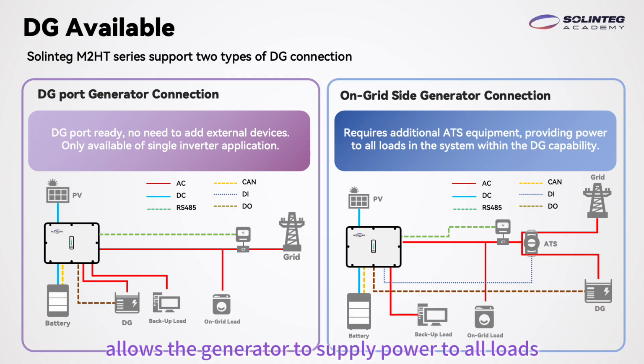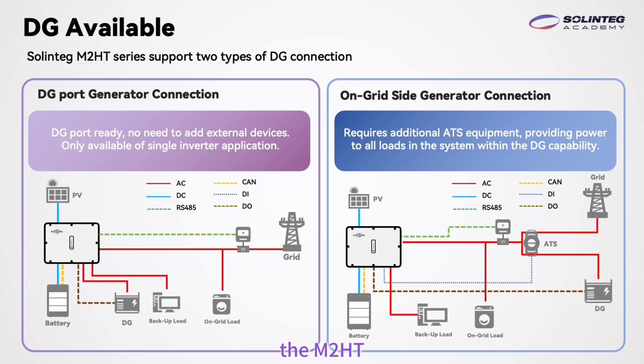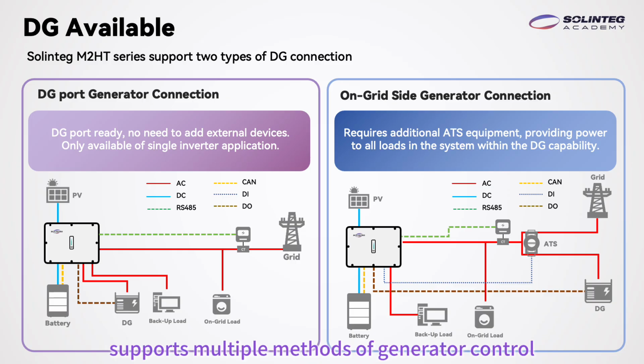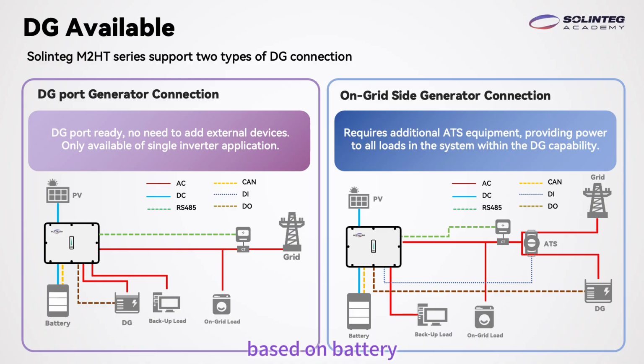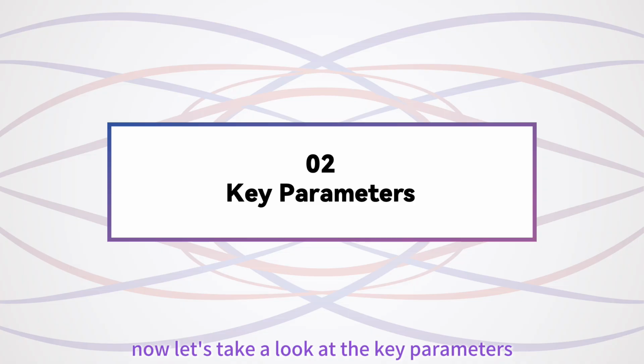This arrangement allows the generator to supply power to all loads in the system when there is a power outage. In both cases, the M2HT supports multiple methods of generator control, so installers can configure the system to start and stop the generator automatically based on battery SOC or grid availability. The system can also use the generator to charge the battery directly, ensuring that every unit of fuel is used as efficiently as possible. For the end user, this means lower energy costs, greater resilience, and a system that intelligently manages all available energy sources – solar, battery, grid, and generator – to optimize their bills and keep their business running. Now, let's take a look at the key parameters.